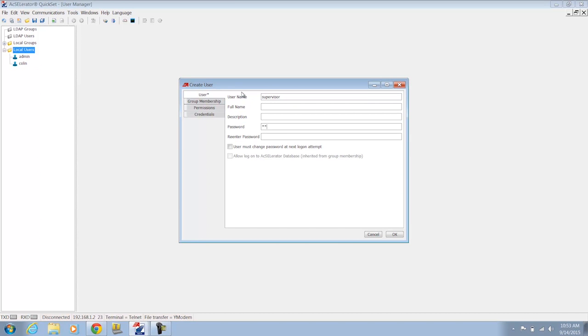Now when I create these users try to make sure that you're using strong passwords. The SEL 3620 requires that you use a combination of uppercase letters, lowercase letters, numbers, and special characters and the passwords at least have to be 8 characters long. So do be aware of that. Okay so I've created my supervisor user.